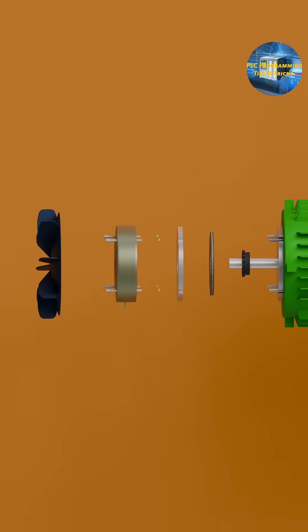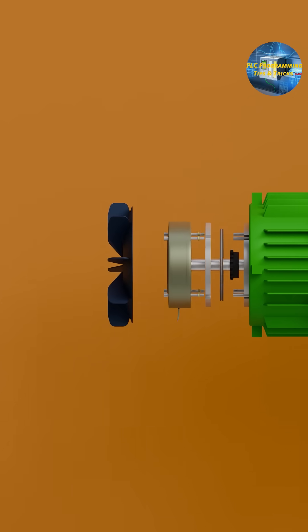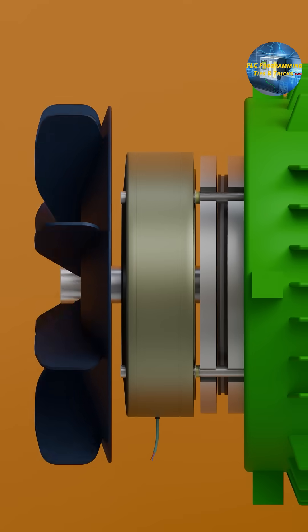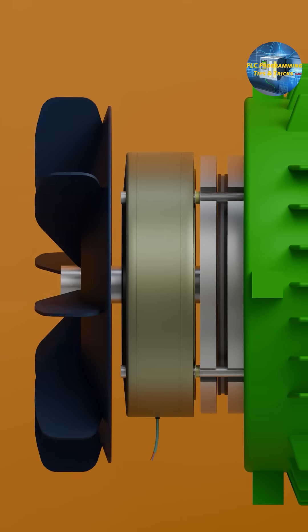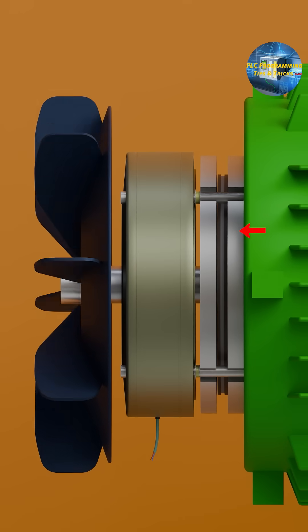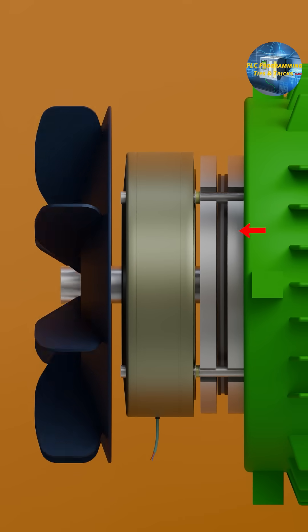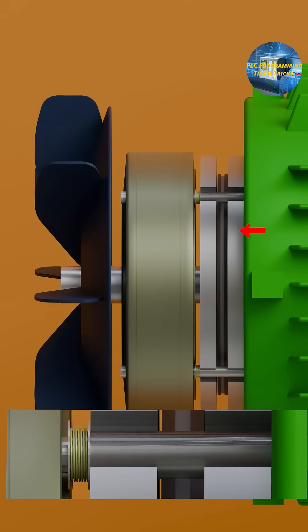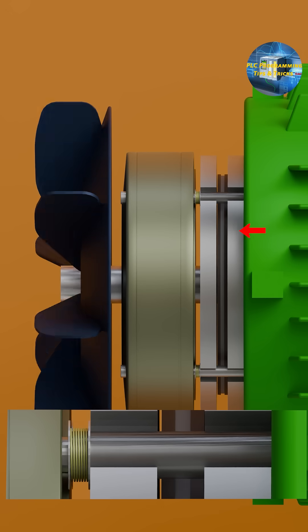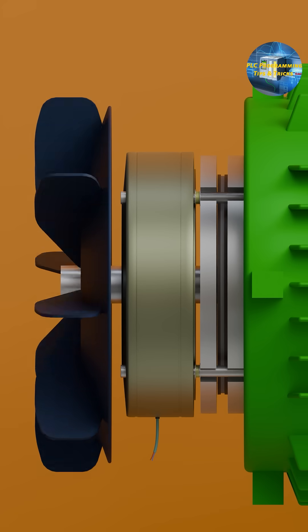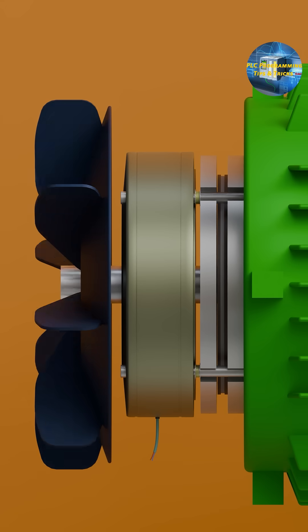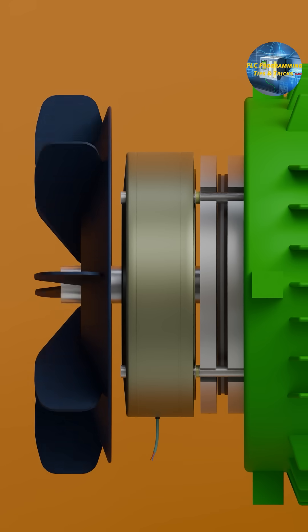Here's how it works step by step. When the motor is running, the magnet coil is energized. This pulls the pressure plate away, releasing the brake pad so the shaft rotates freely.